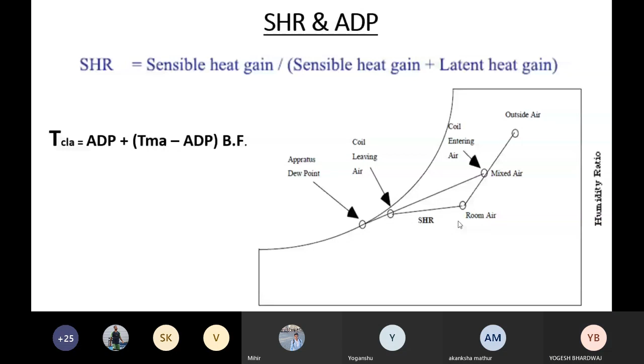Then we have to put a point where that line cuts or intersects our saturation line, that is called our ADP. So we don't use the psychrometric chart every time to calculate the ADP. We have our charts, which I will show you, and those charts can also directly give you the value of ADP if you know the value of your sensible heat factor and your room design conditions.